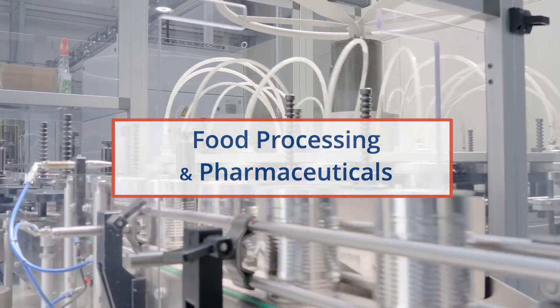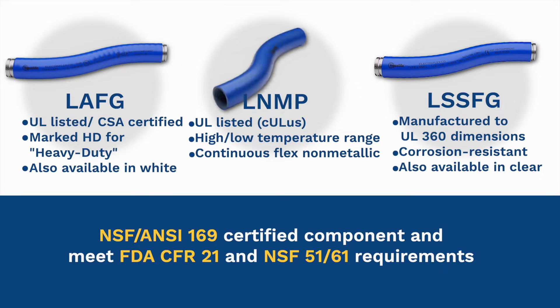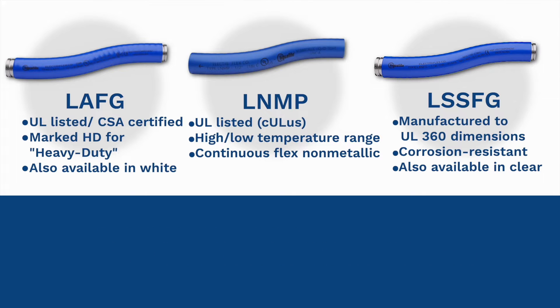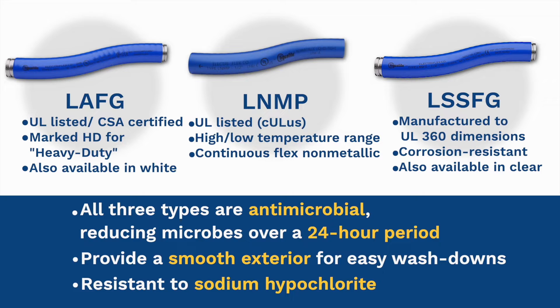Electrical conduit in the food processing and pharmaceuticals industries must meet hygienic standards to eliminate contamination. Types LAFG, LSSFG, and LNMP conduits are NSF ANSI-169 certified components and meet FDA CFR 21 and NSF-5161 requirements. All three types are antimicrobial, reducing microbes over a 24-hour period. They provide a smooth exterior for easy washdowns and are resistant to sodium hypochlorite.